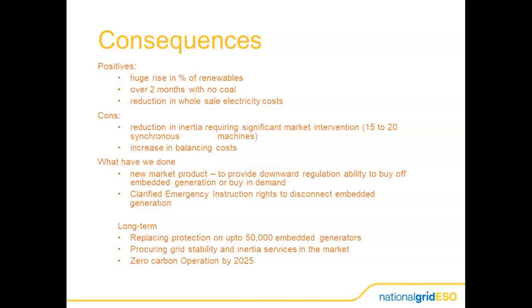We also have something called vector shift, a voltage-based form of protection, which doesn't ride through the faults that we'd like it to on a low carbon transmission system. So we're replacing those 50,000 sets of protection.